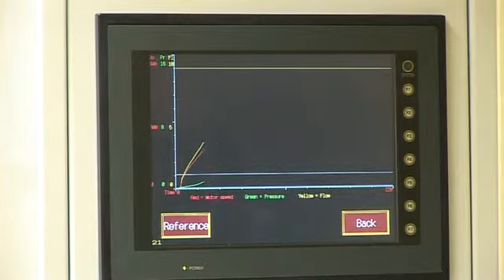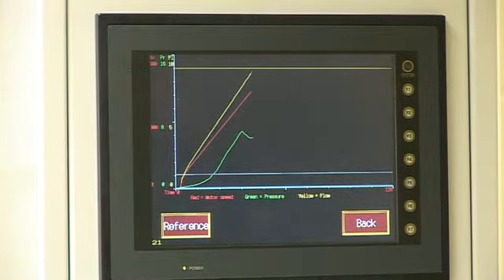The API 675 requirement is that linearity should be maintained at plus or minus 3% of the designed flow rating of the pump.